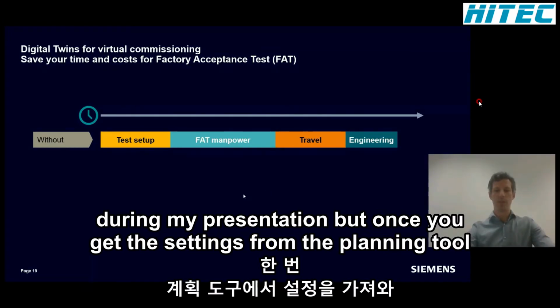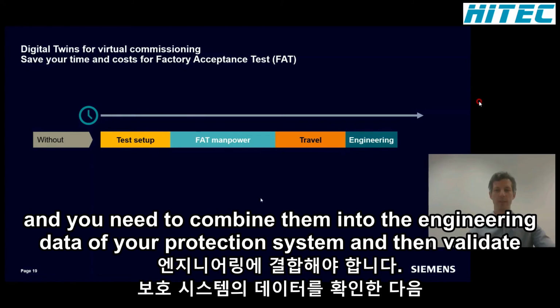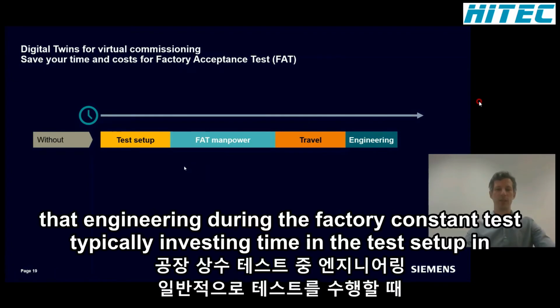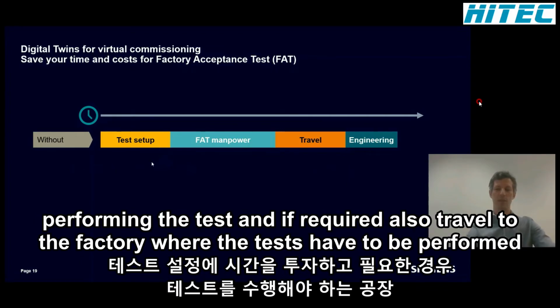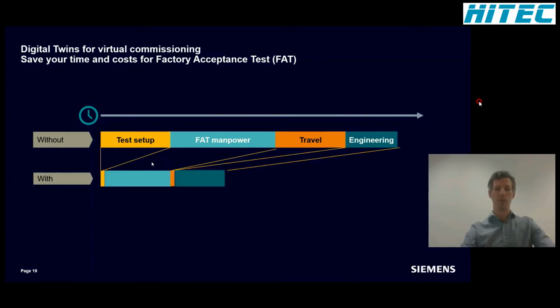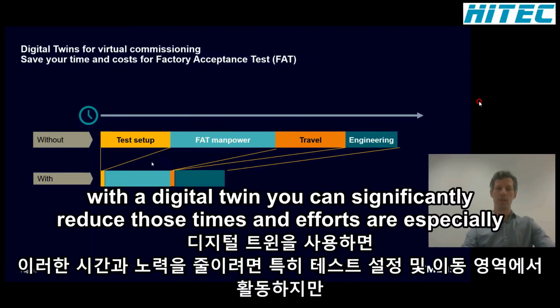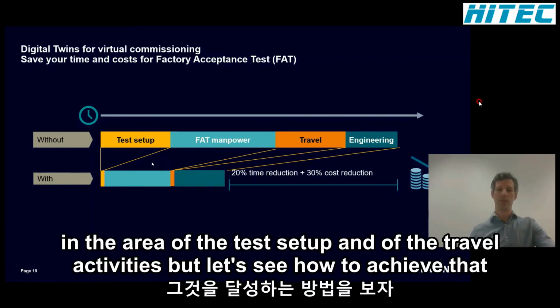Once you get the settings from the planning tool, you need to combine them into the engineering data of your protection system, and then validate that engineering during the factory acceptance test, typically investing time in the test setup, performing the test, and traveling to the factory if required. With a digital twin, you can significantly reduce those times and efforts, especially in the test setup and travel activities. Let's see how to achieve that.